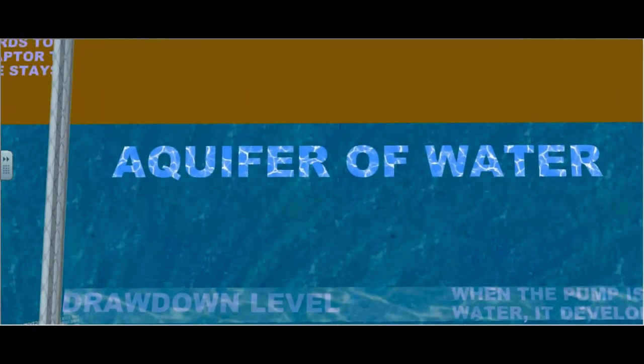This is an aquifer of water. When the pump is pumping water, it develops drawdown, which is the distance in feet or meters that the aquifer of water lowers. It actually develops a cone which goes down to the drawdown level, which must be above the foot valve.